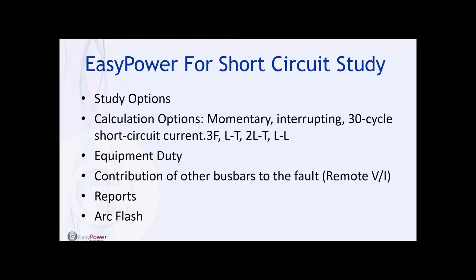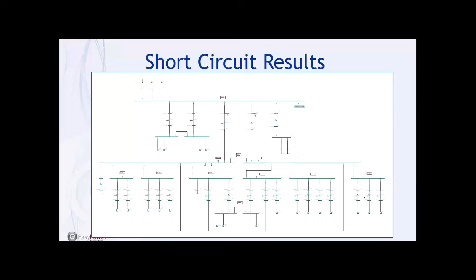So in our EasyPower report, we include all of this information we got from EasyPower. This is, for instance, a picture of the results. In our results, we have everything in green, meaning that the nominal size of all equipment is okay according to the different short circuits we have in the power model. And this is a typical report we got from EasyPower.